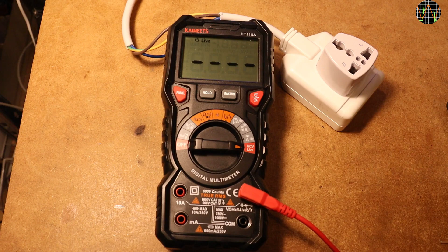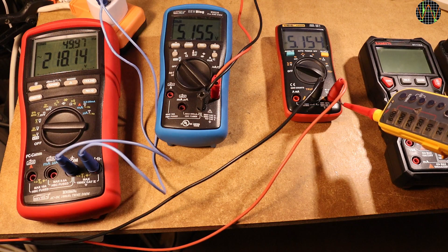Perhaps surprisingly, it does the same for the blue multimeter, which only shows 5 volts DC on the display. While on the small red multimeter on the right, which is also showing 5 volts DC, the NCV mode shows only low voltage and a slow beep. If I use my Fluke tester, we see the expected warnings at the leftmost multimeter, and the same AC warning light comes on when touching one of the leads of the blue multimeter, while nothing happens on the meter on the right.